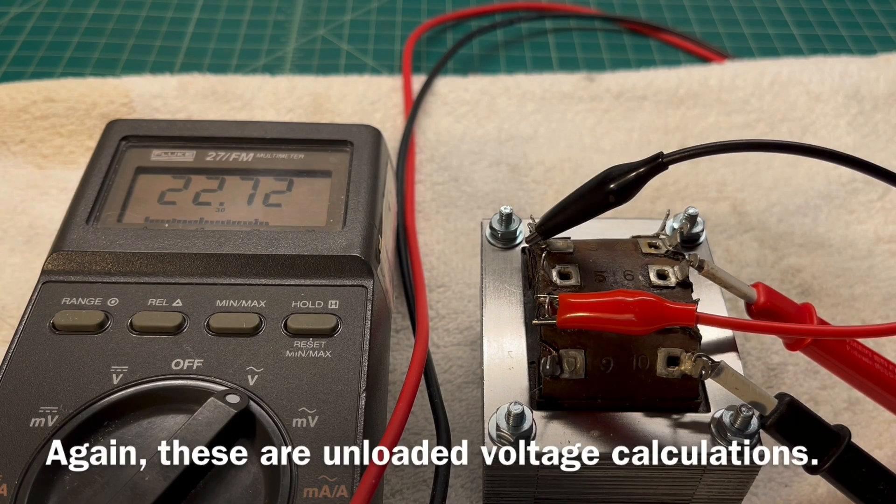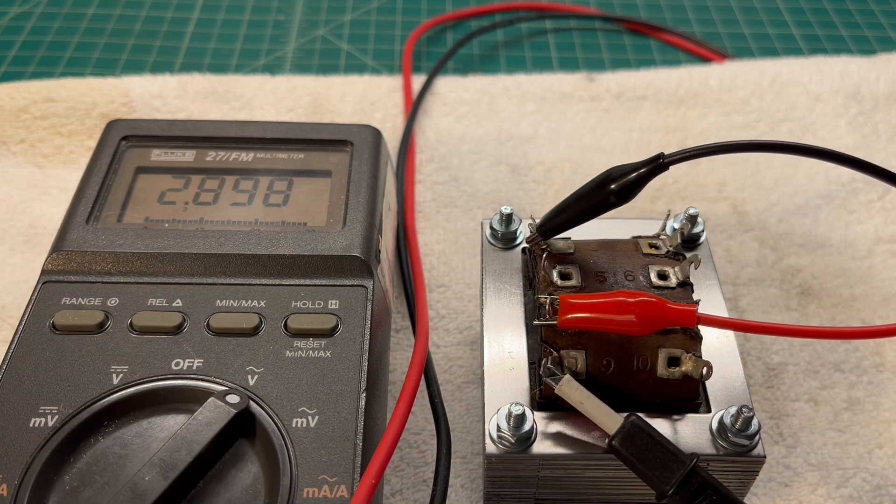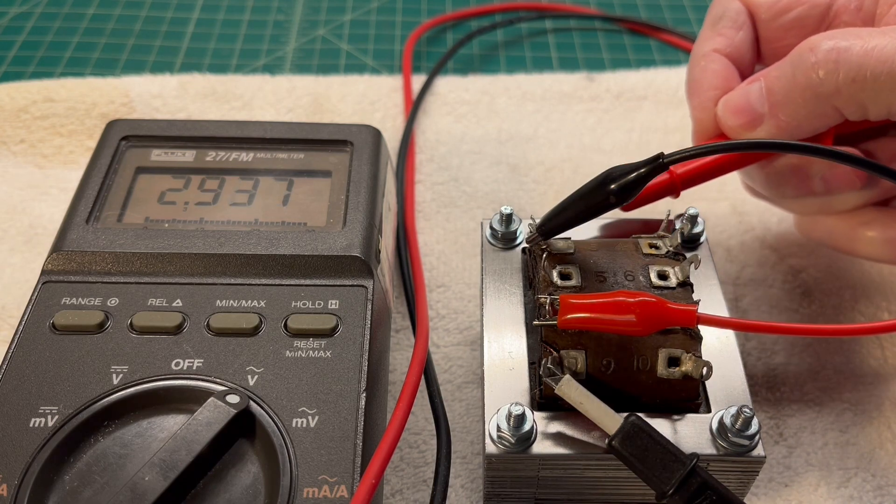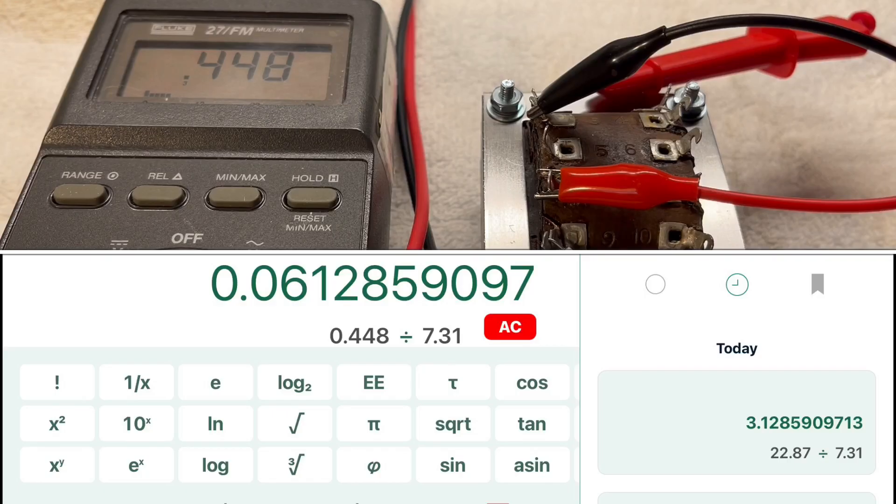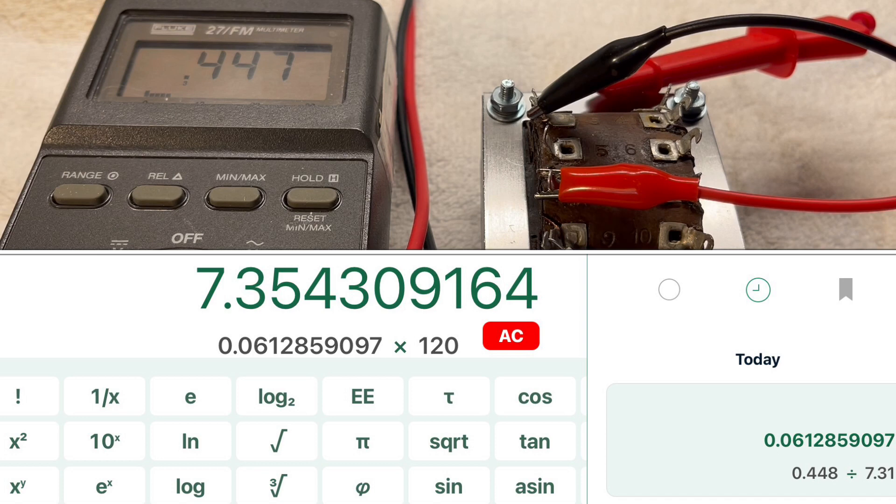We'll do one of the secondaries on the low voltage side as an example. We'll go one to nine here, that would be the 6.3 volt winding. You can see we're at 0.448. Divide that by 7.31, and that gives us a ratio of 0.061285. Multiply that by 120, and you can see unloaded, theoretically we have around 7.35 volts.